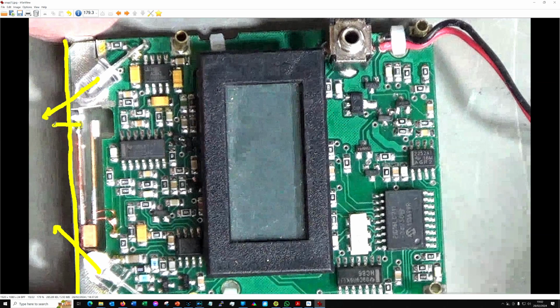And just here there's a small hole about 4mm drilled, and about a 3mm stud just level with the surface, centered in that hole and insulated from it just by the air. So this device on the inside, with its two legs going up, is actually the sensor. If we think about it, the front end of this is in the electrical field, but the majority of it, this plate, is actually referenced to ground, while the stud is not referenced to ground - it's actually charged to the same voltage as the surrounding electrical field.